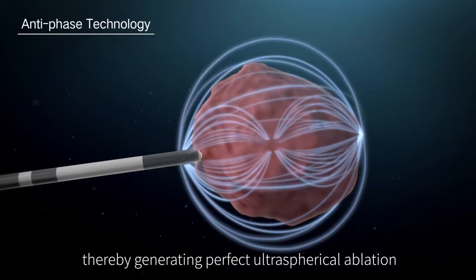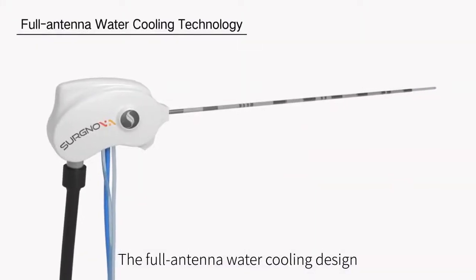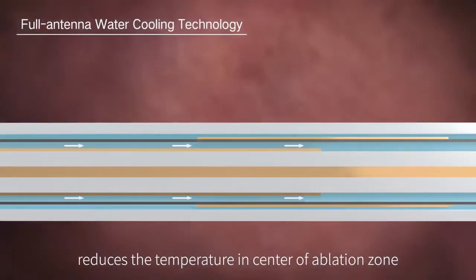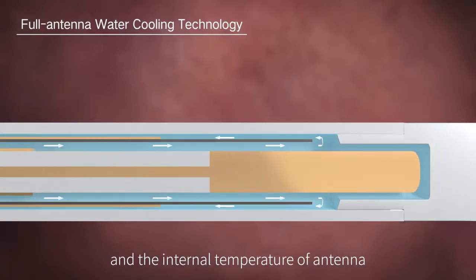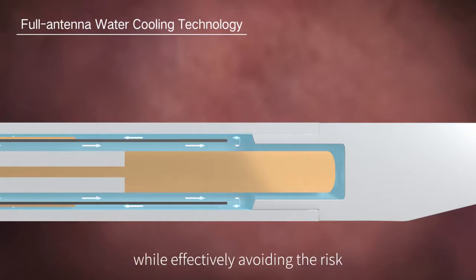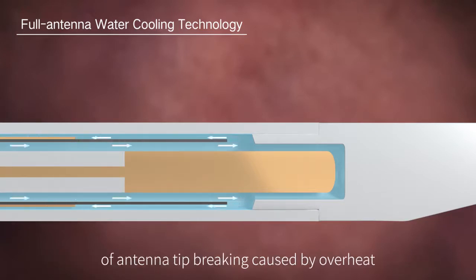The full antenna water cooling design reduces the temperature in center of ablation zone and the internal temperature of antenna, thereby minimizing carbonization and maximizing ablation size, while effectively avoiding the risk of antenna tip breaking caused by overheat.